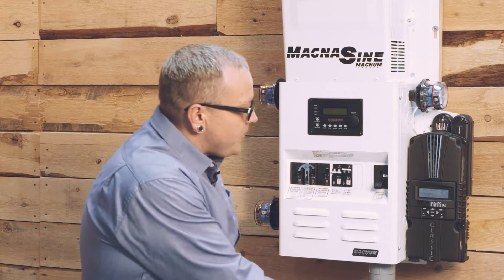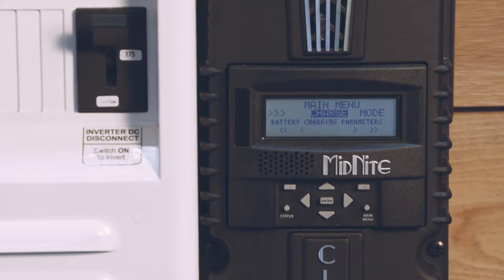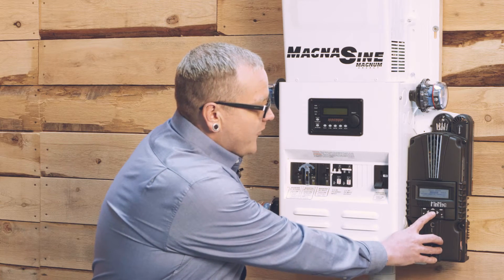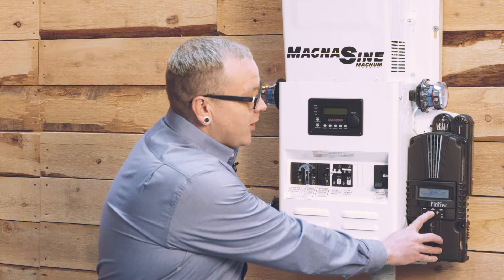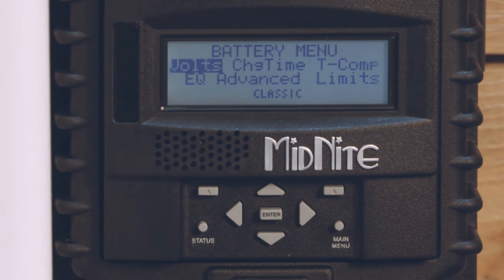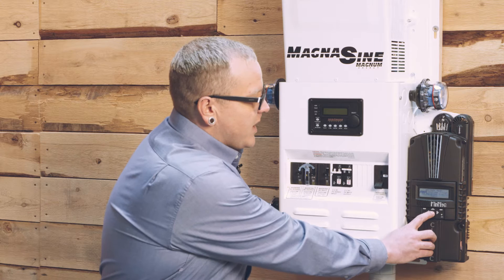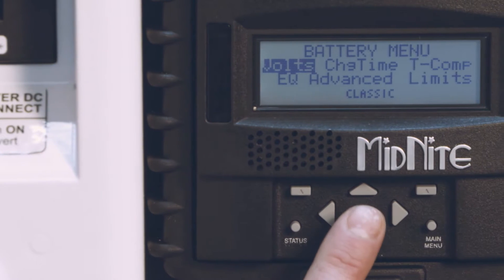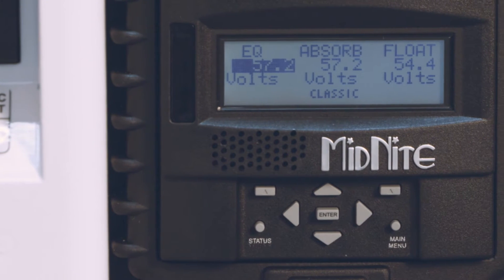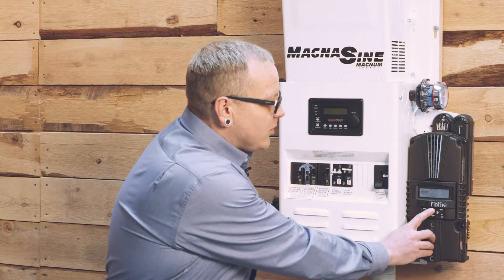The first thing we're going to do is get into the main menu of the MidNite Classic by pressing main menu, and the first menu item that comes up here is the charge menu. We'll press the enter button between the four arrows to get into the charge menu, and then the first thing that comes up in the menu there is volts, and that's where we want to be, so we'll hit enter again. Once we get in here, we'll see the default values for equalize, absorb, and float voltage set points.